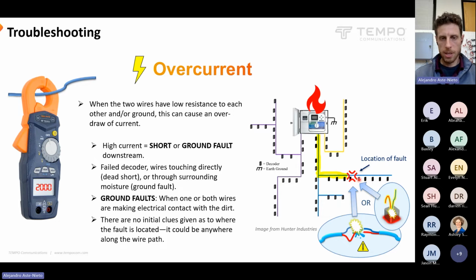It's going to affect everything on this 2-wire path, because the whole thing is just using up a lot of current, and that's all it knows. All it knows is there's a lot of current going out there from the controller. It doesn't know where that high current ends or not. It just knows it's out there, and that's probably the situation where a clamp meter is going to be most helpful, since we have the least amount of information coming from the controller.